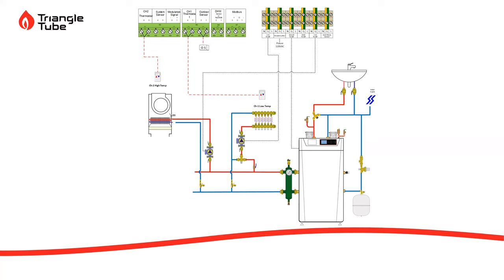Also, you can see here on this install, we tied in our water connection in here, this is a good place. You can totally tie your water feed into here with your thermal expansion. I tend to like to do it on the return side right here on most installs, especially with these low loss headers. That way, when I'm filling the system or running it and I get air up in here after the install, I'm treating that water as it comes in, but any air that comes back in through is going to be treated in my low loss header as well.